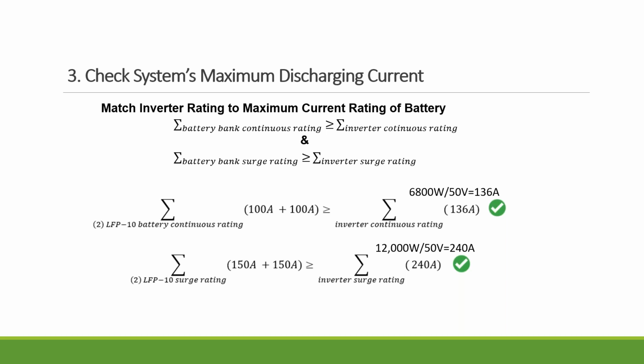The 6848 can surge 12 kW. You take that number and divide by the battery bank voltage, 48 volts or 50 volts. 50 volts is more accurate. At 50 volts, you're at about 240 amps. That means the inverter can draw 240 amps for about 1 minute out of the battery bank. With the two of the LFP-10, you do not have that concern because they can handle 300 amps surge. So you're totally fine with that.